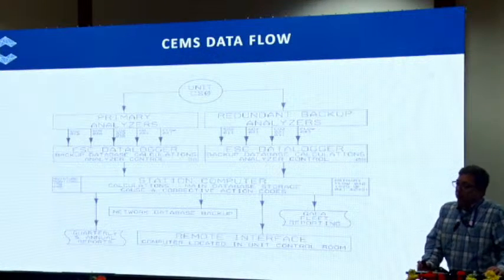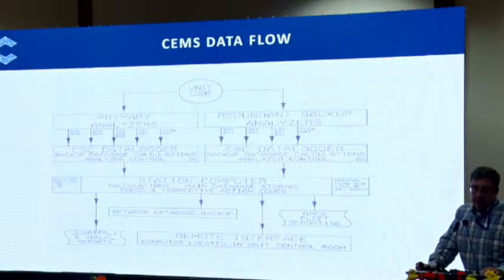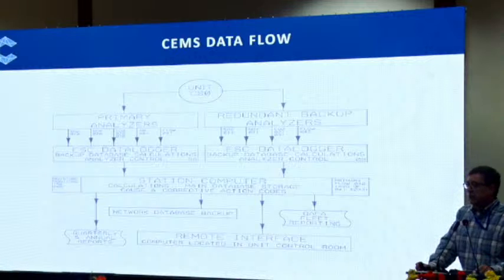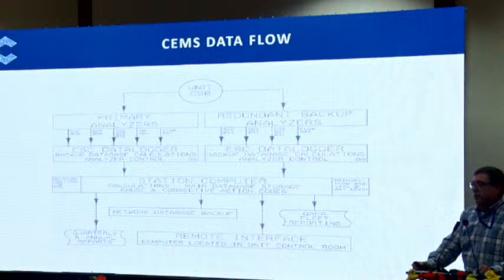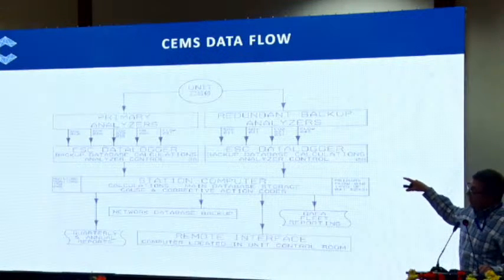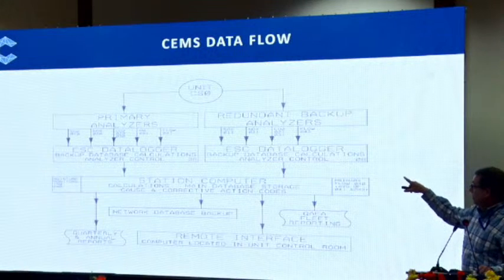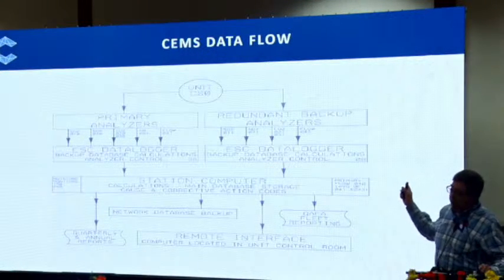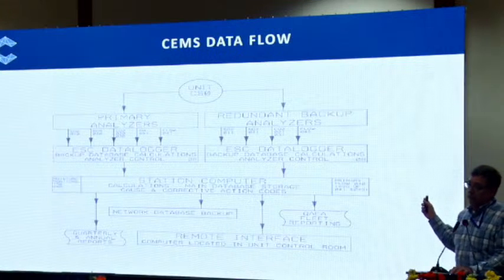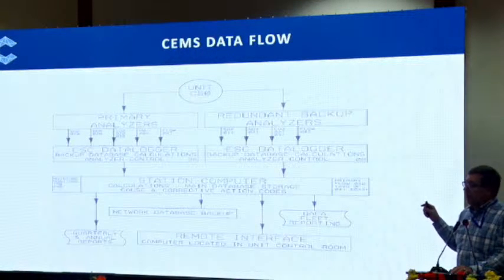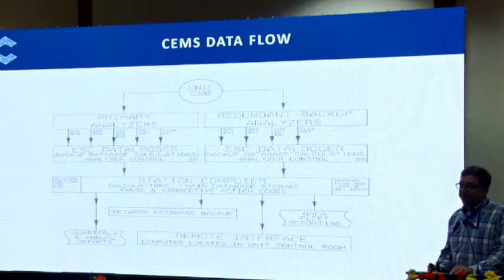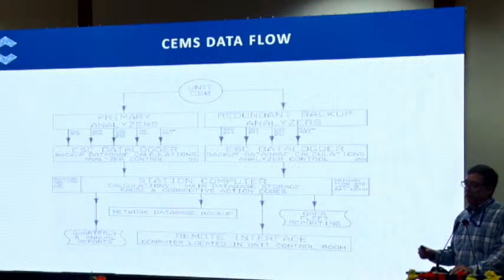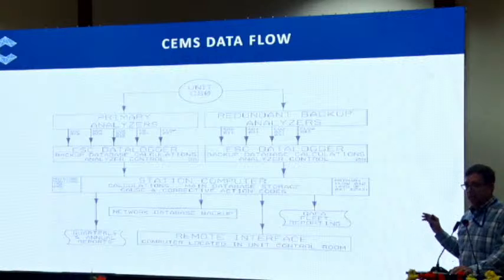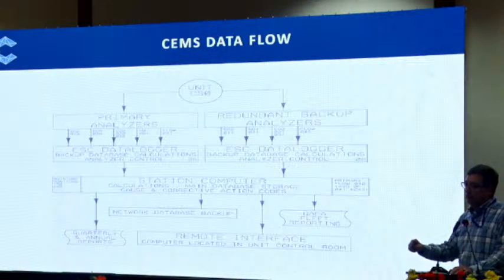This is an example from a monitoring plan data flow, which we have to include to the EPA and to the regulatory agency to show how the data is gathered and processed in a general sense. So you can see we have two systems. We have a primary analyzer and a redundant analyzer. We have SO2, NOx, CO2. These are fed to individual data loggers, so you have a complete backup system. That is fed to the station computer. From the station computer, we have a network database that provides backup and data storage for long-term usage.